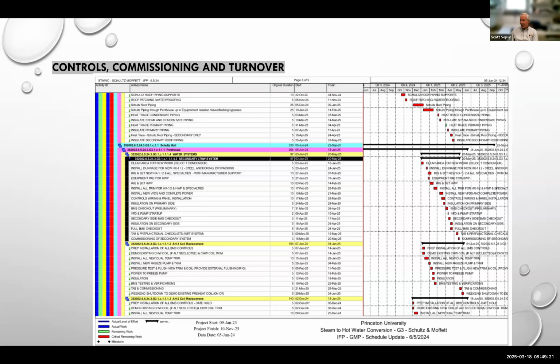And if you don't have staff on site able to monitor equipment, you should at least have someone reviewing the BAS trends and looking for anomalies. And consider supply chains for new equipment. How long will it take to get a pump if it fails? You may want to stock stuff even before your warranty runs out. So you're going to be challenged by projects that wind down, by unintentional software bugs, by new programs that overlay old programs, and the new products and types of equipment, and deciding where to draw the line between the BAS and the onboard controls.